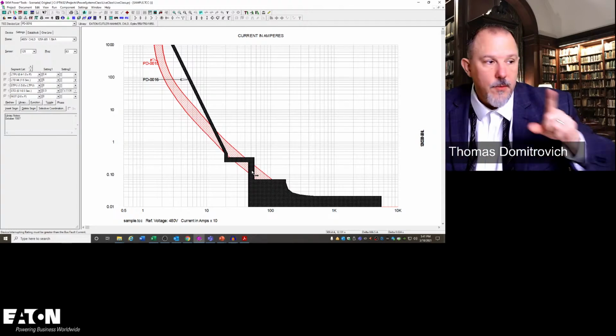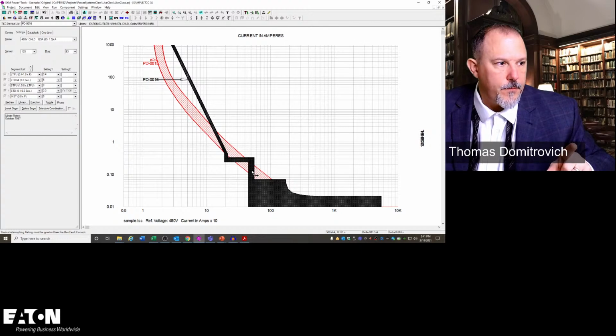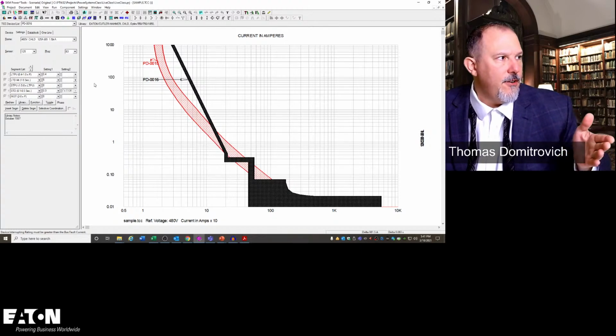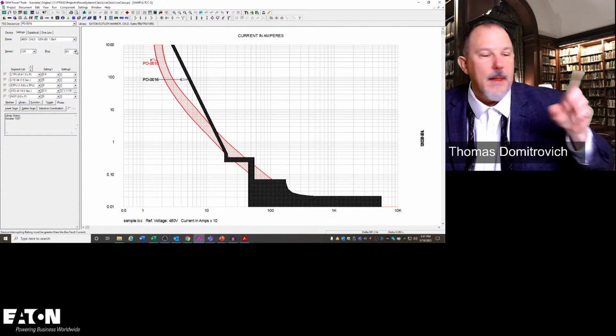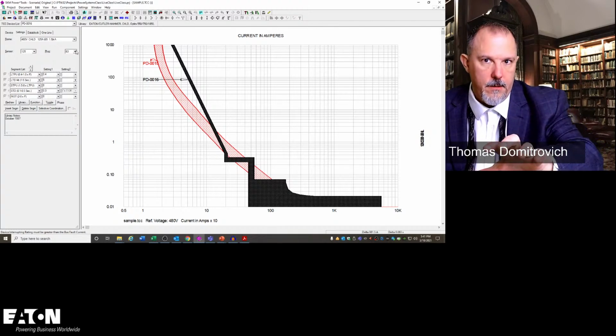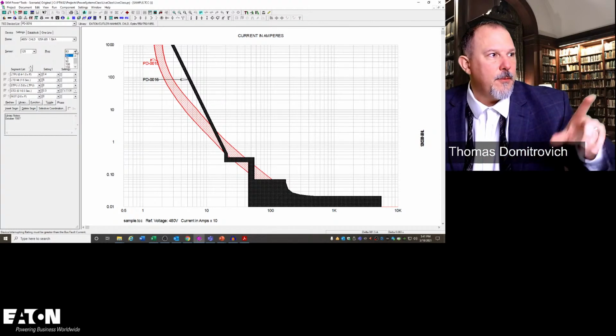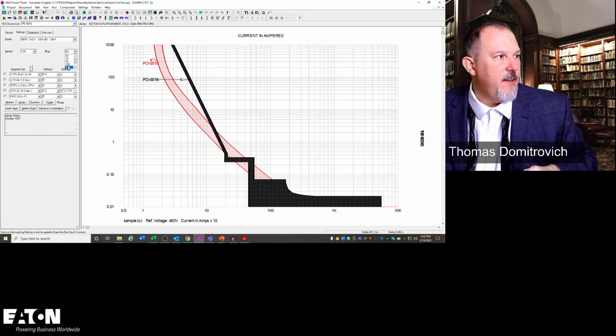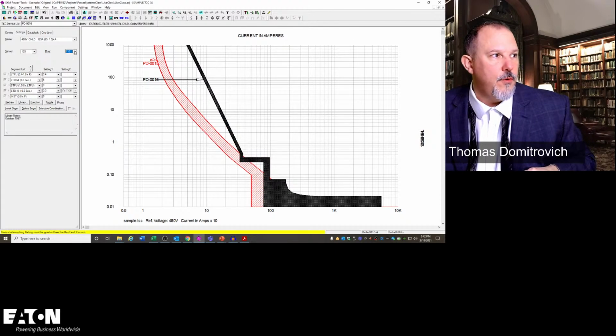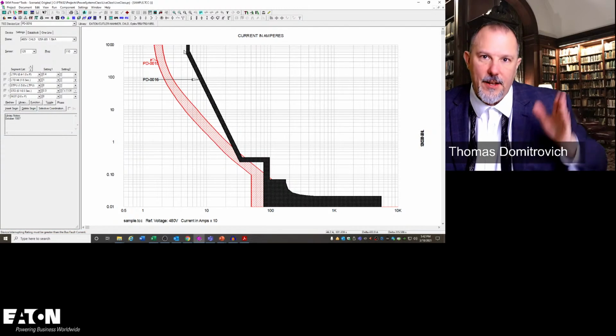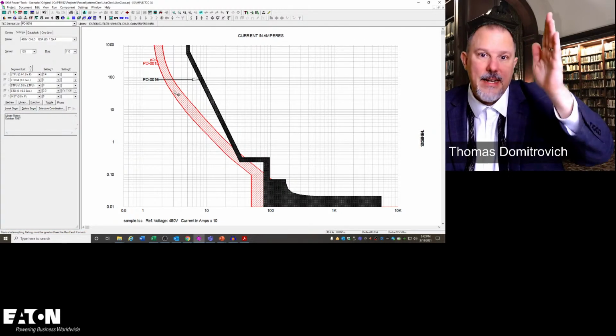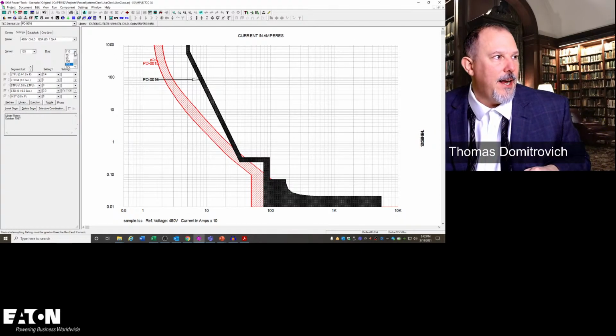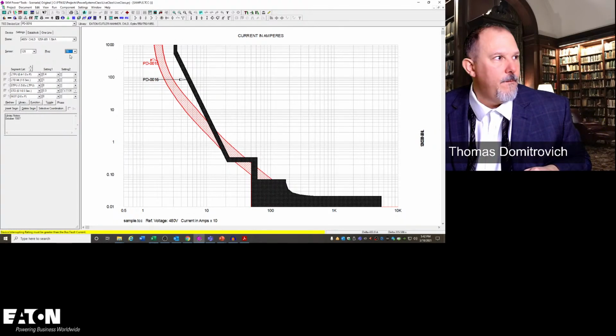So what I'm showing you here is that this breaker is what? It's 125 amps at 63. Now, that's a 125 amp frame. And it's a 63 amp trip. Way up there is 63. If I move this to 110 amp trip, look what moved. Okay, there's my amp trip up there, right? So that now at least you have the little, that's my pickup. And that's at 110 amps. I lower it down to 70. I bring it back up to 90.